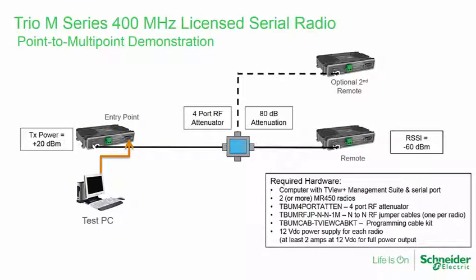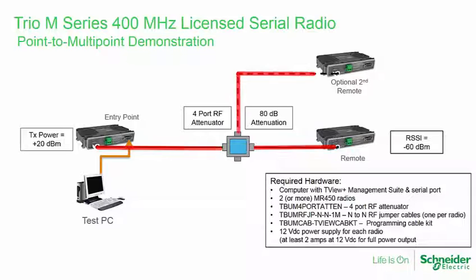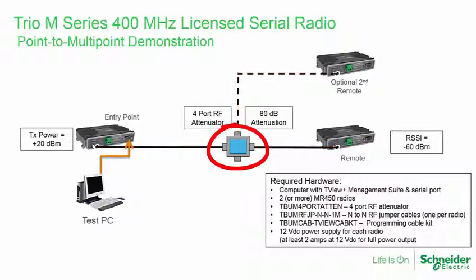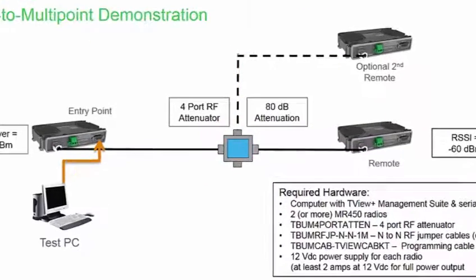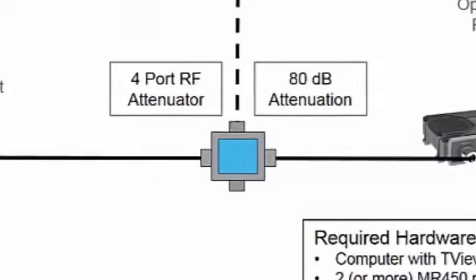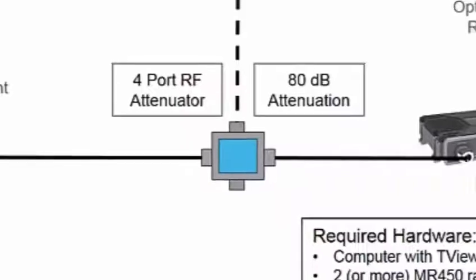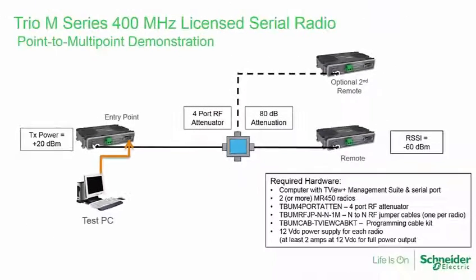Here, the hardware used for this demonstration is shown. The TRIO radios are connected via coaxial cables to a four-port RF attenuator, which is available from Schneider Electric. This device provides 80 decibels of attenuation between any two ports, and it prevents test transmissions from being sent over the air, where they may interfere with licensed users of the channel.